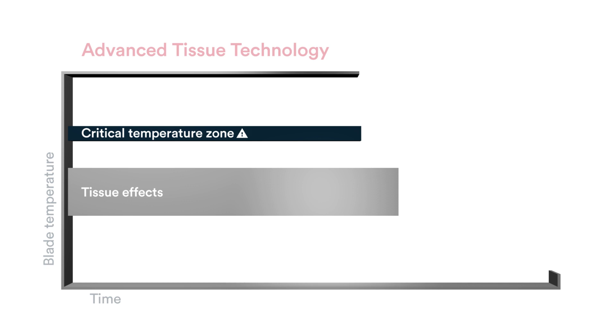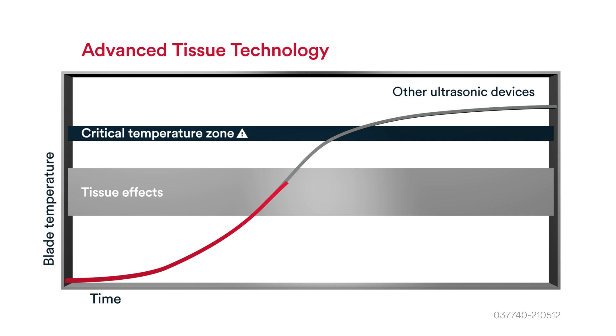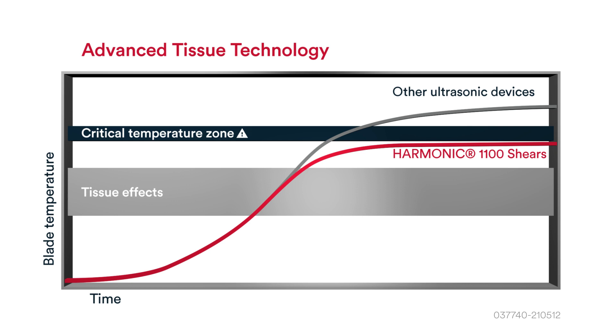The Ethicon proprietary Advanced Tissue Technology, or ATT, algorithm actively manages the device's thermal profile by measuring and responding to impedance throughout each activation. It prevents overheating of the blade, which may help to protect surrounding tissue and vital structures.